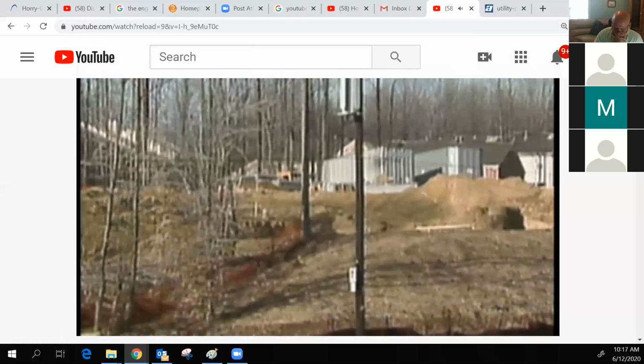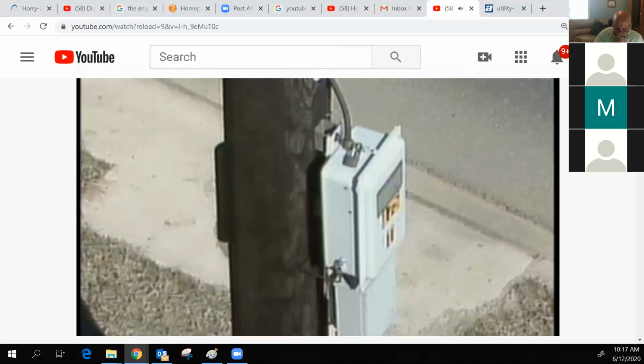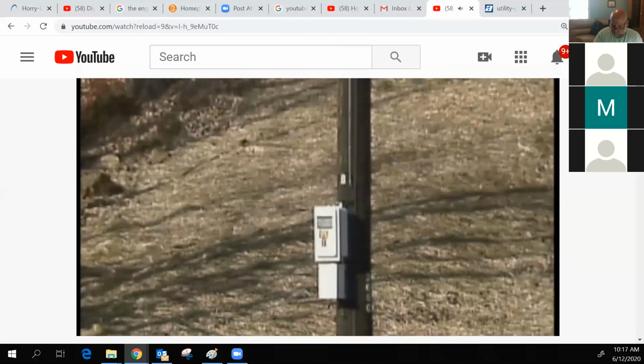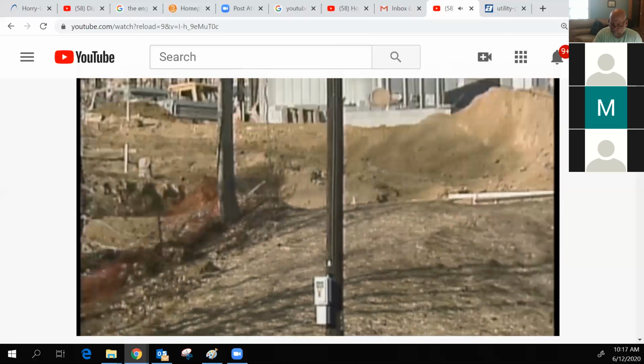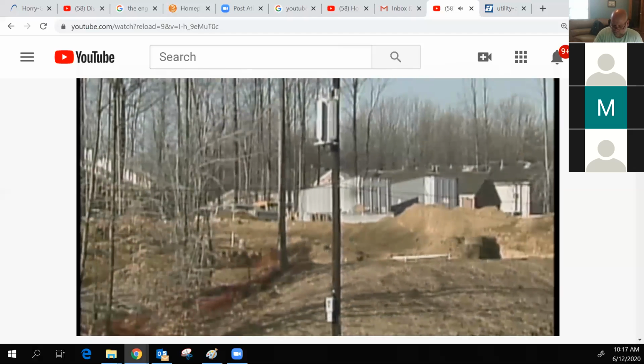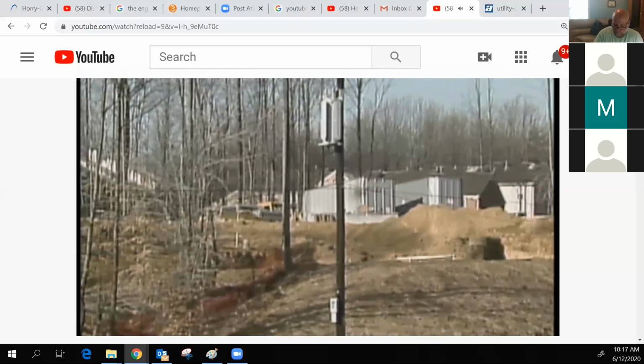This voltage regulator has a solid-state control mechanism mounted in a metal box lower on the pole. It is permanently attached to the regulator by a control cable. When the regulator is changed out, the control mechanism and cable are changed at the same time. The control mechanism permits the voltage regulator to respond automatically to changes in line voltage. The control mechanism can also be used to operate the regulator manually. The mechanism is powered by a fused 120-volt source.